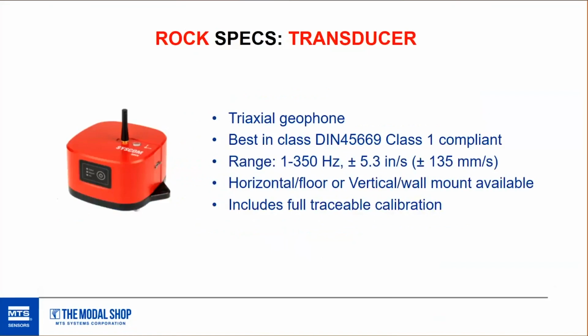Some of the specs overview for the transducers being used. Geophone sensors are used to monitor transverse, vertical, and longitudinal velocity. It's a best-in-class sensor used with wide frequency and amplitude range. So with Rock, there's really no need to use different geophones when testing to different standards. We use a configuration in the SCS software instead.